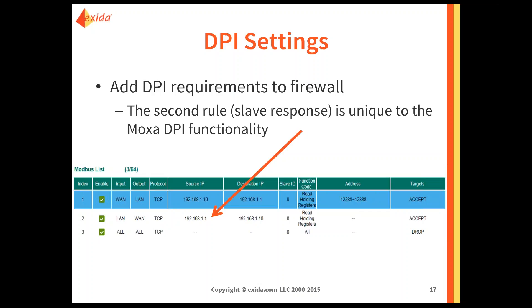The next thing we look at is the function code we want to use. Moxa knows what function code 3 is — it's read-holding registers. Now you put in the address of the registers you want to read. We said we started at 12288 for a quantity of 100. We've actually put 12288 to 12388 here — it should be 12387 to be exactly 100, but that's okay. Reading isn't really a problem. And we want to accept the traffic passing through.